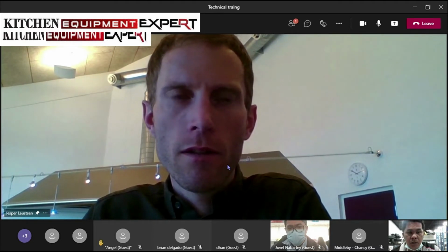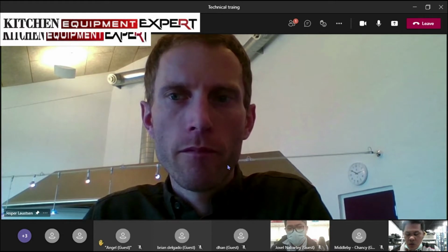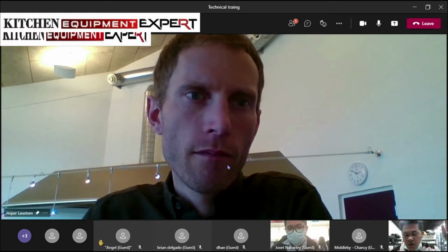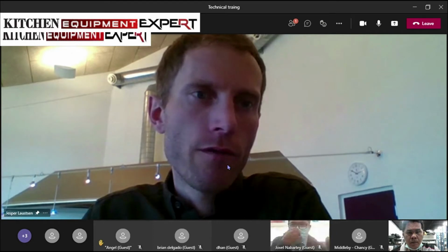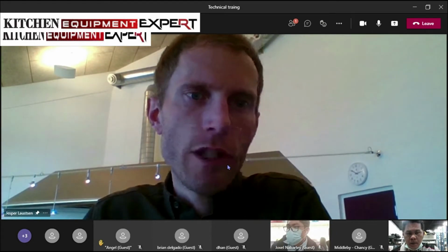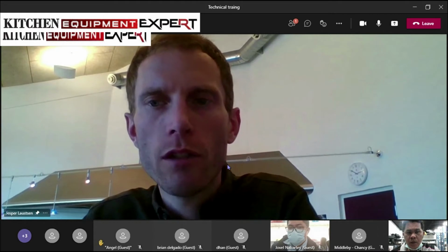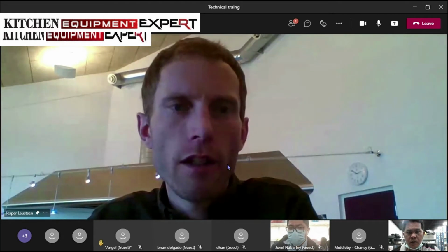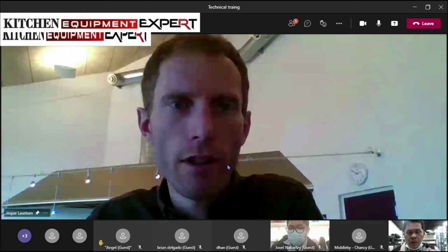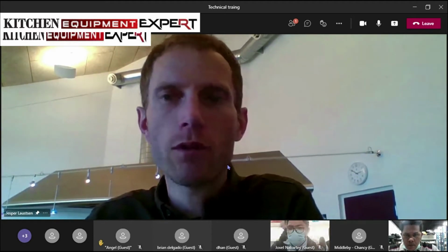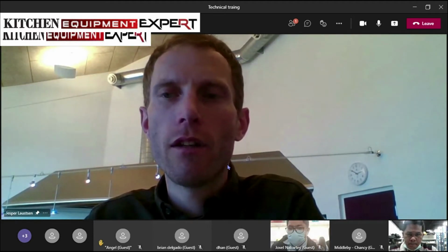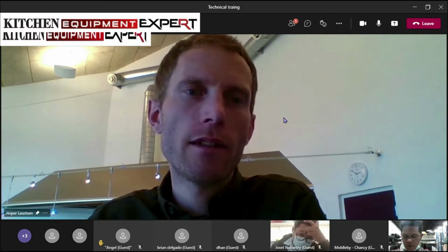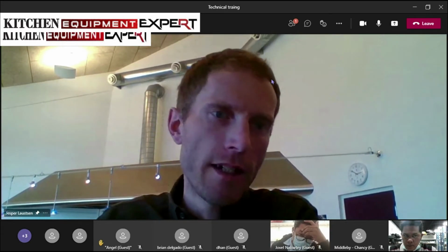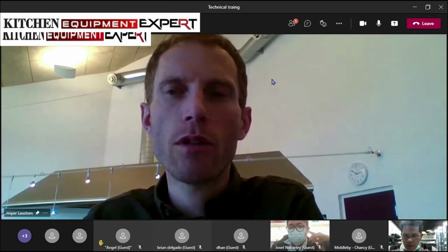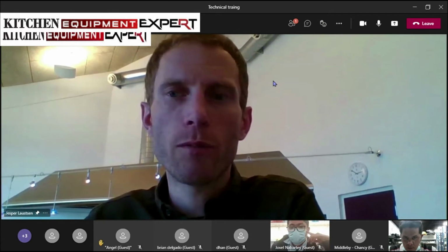The display should show error 45 or the 24 volt still. Error code 45. Have you checked the fuse? Yes, the F1 fuse, yes. Okay. Can you measure the 24 volts after the transformer? Yes. Is there an LED light at the I/O board stating that 24 volts is present? Yes, it's blinking green. Yeah.